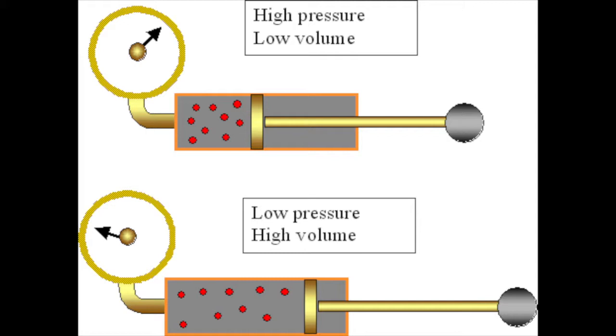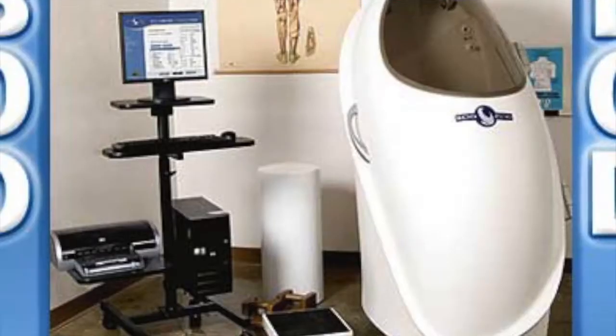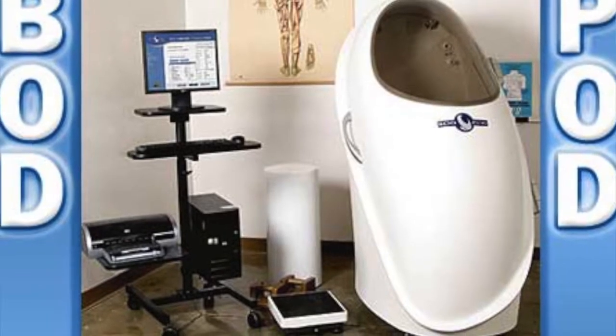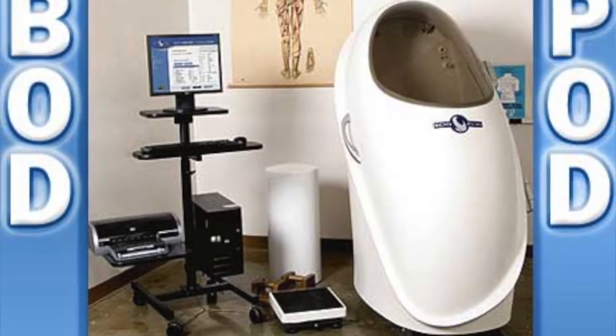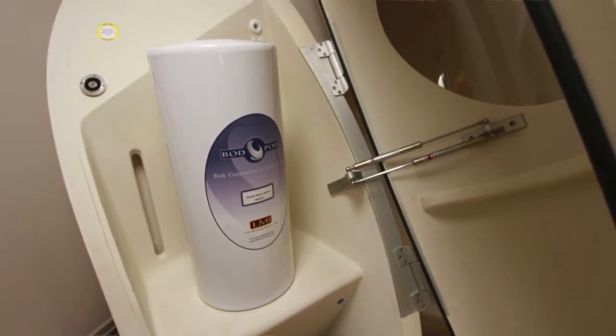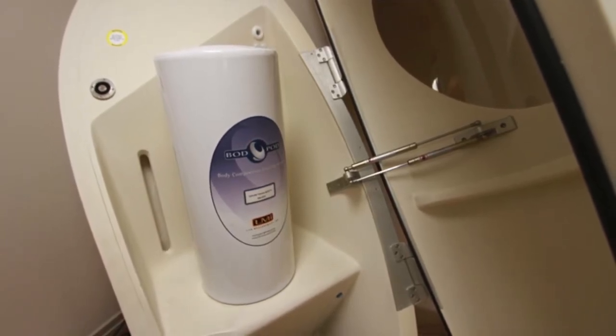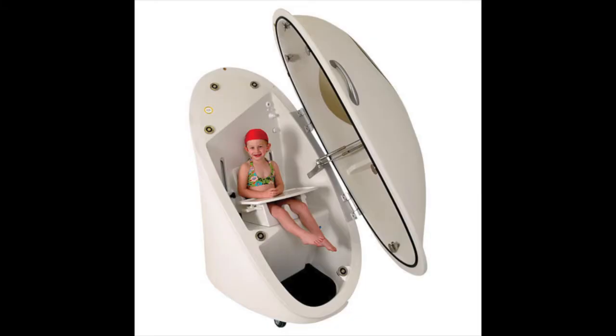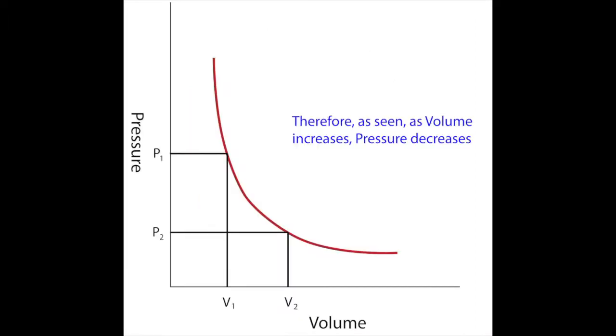For example, the pressure response in a large chamber is smaller than that of a small chamber. Through this, an initial measurement of pressure and volume can be taken for the empty test chamber of the Bod Pod. The Bod Pod measures pressure changes and volume inside the chamber to determine that the system is accurately measuring the volume of the 50-liter cylinder. Once calibration is completed, the subject being measured sits inside the chamber. The Bod Pod then performs the same pressure-volume measurements again to determine pressure inside the chamber with the subject inside.